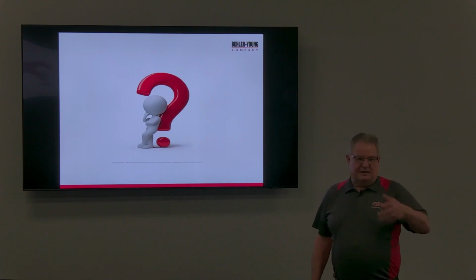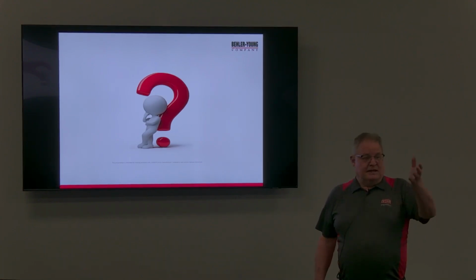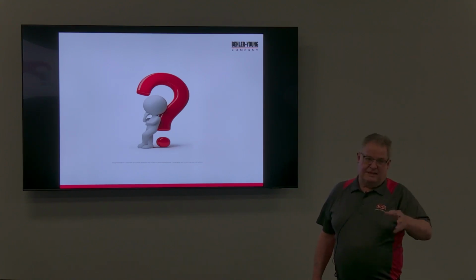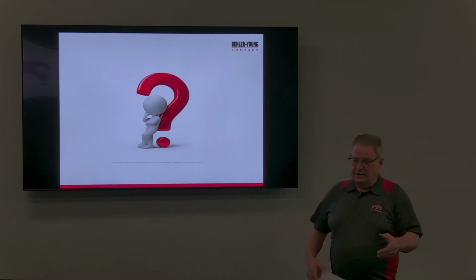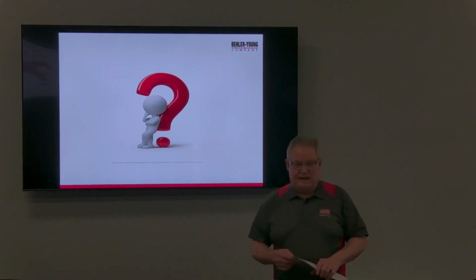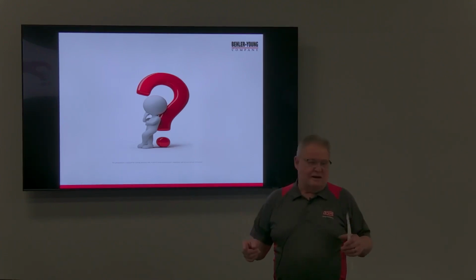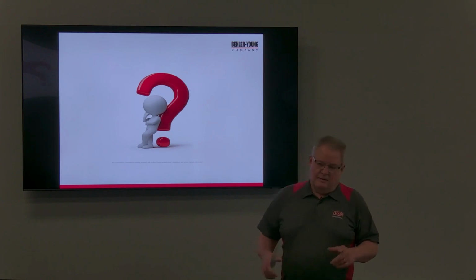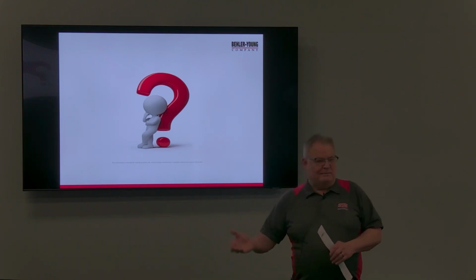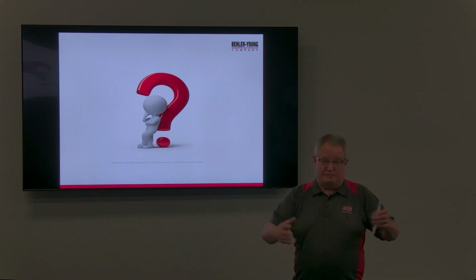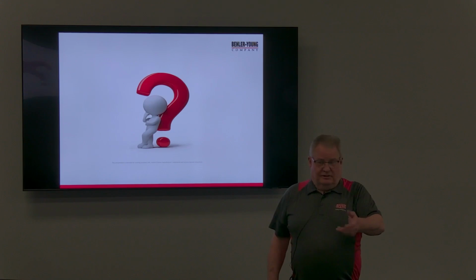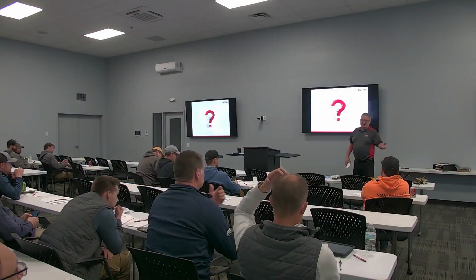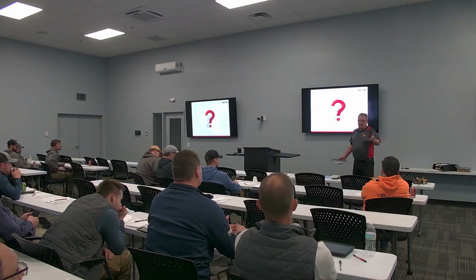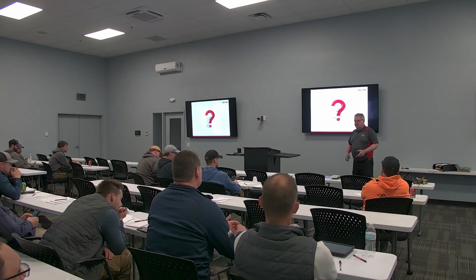That's also why you can't mix refrigerants. I get some guy asking about the new stuff: 410A was 50% R32, our 454B is 68% R32. The other 32% is 1234YF. Has anybody ever heard of that? If you've got a car newer than about 2016, it's what's in your car. So I've had guys ask me, why can't I put R32? Because now you've changed the mix completely. So you can't mix them. If one of your helpers accidentally puts R32 into your 410A, 410A is 50% R32, so it's not dangerous, but you can't use it that way.